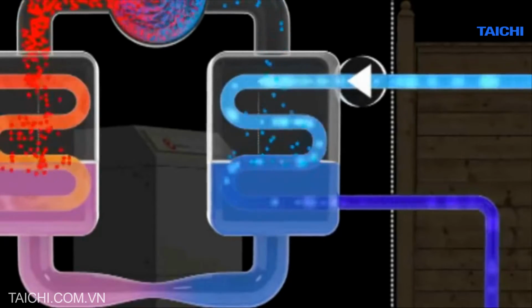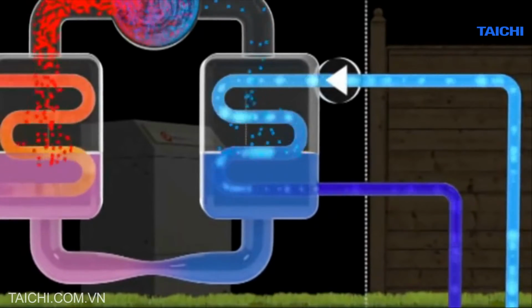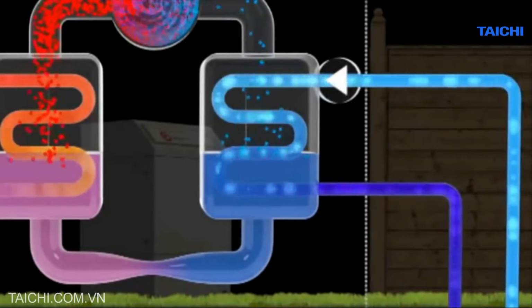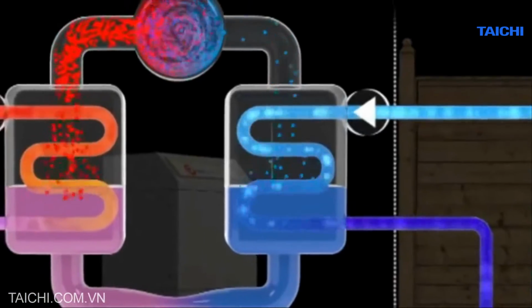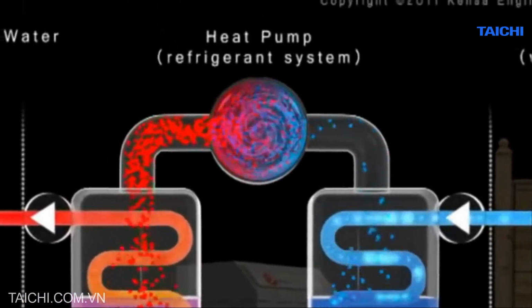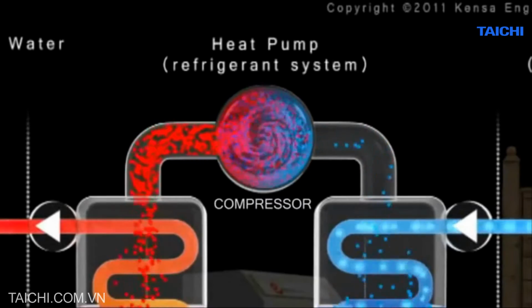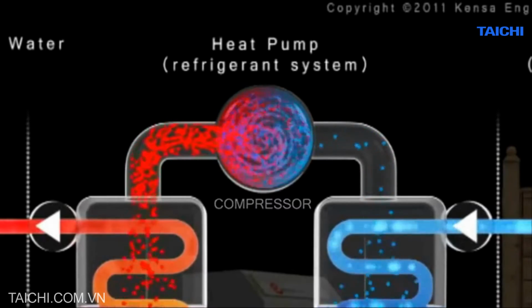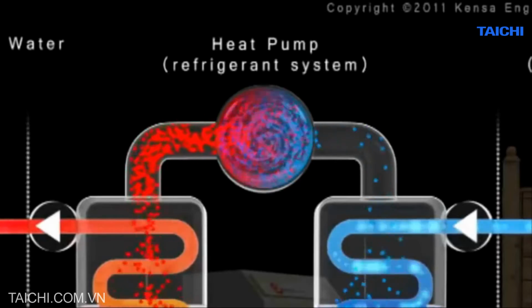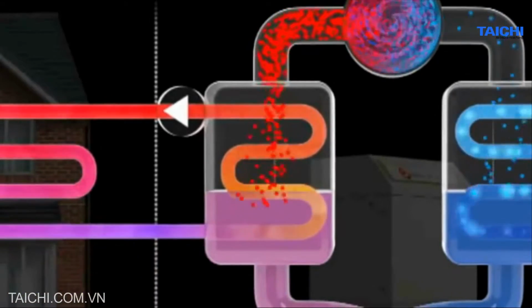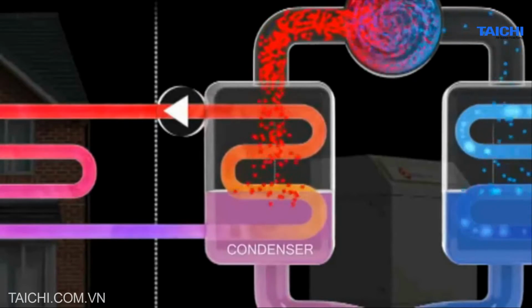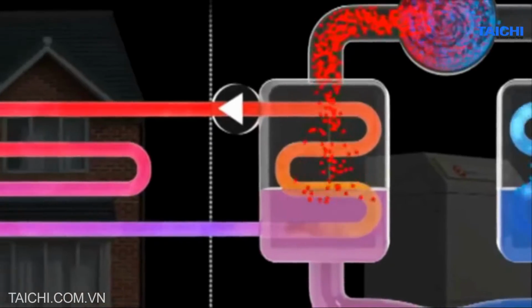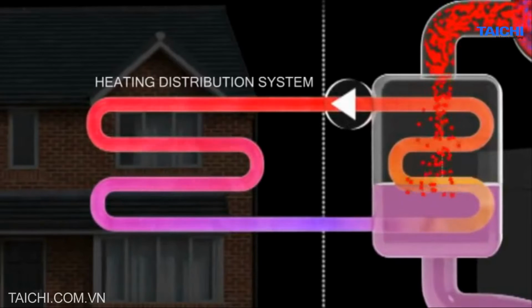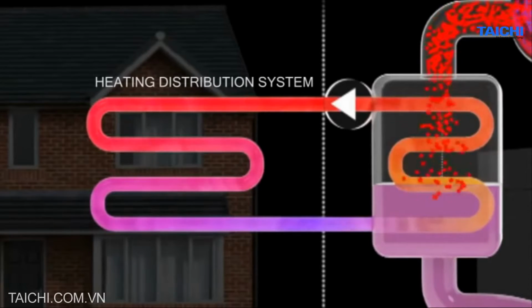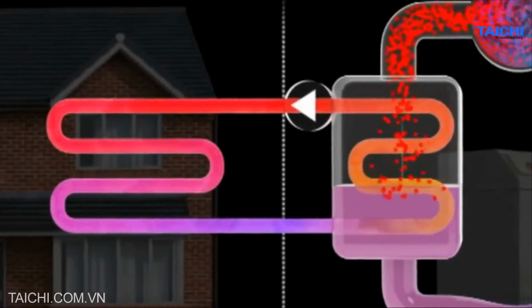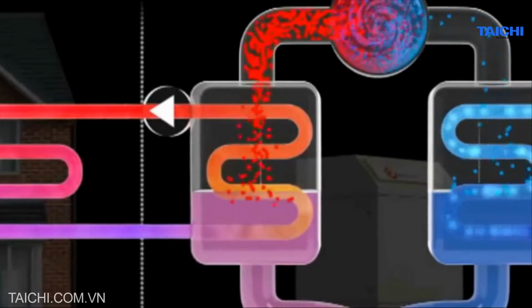The refrigerant never physically mixes with the water antifreeze mixture. They are separated like sandwich layers by the plates of the heat exchanger, which permits the heat transfer. This gas is then fed into a compressor. The pressure of the refrigerant gas is increased in the compressor, which makes the gas temperature rise. The hot refrigerant gas then flows into a second heat exchanger called a condenser, which features an identical set of heat transfer plates. The condenser delivers water hot enough to serve the space heating system and, if required, the property's hot water needs. Having transferred its heat, the refrigerant gas reverts to a liquid.